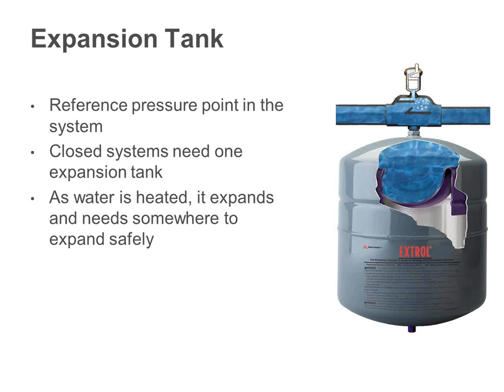We all know we can compress air. We all have air compressors, okay? We can't compress water. So basically here, as this water, the blue water, expands and gets heated, it will push against that air on the other side of that tank. Once it does that, basically that expansion has been dealt with. There's no issues to it. As the water cools back, the air pressure will push back, and you'll always be in this nice state. Normal residential systems, 12 to 15 psi range. Okay, so basically water heats. As we heat water, it expands. We got to give it somewhere to go. That's what the expansion tank is there for.